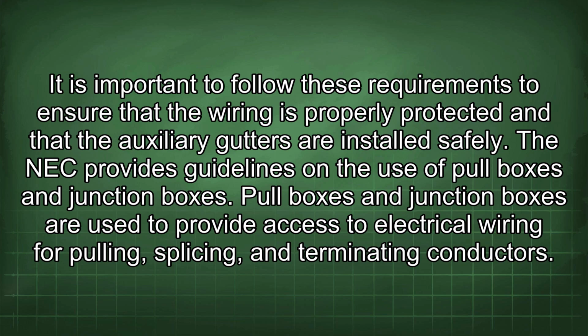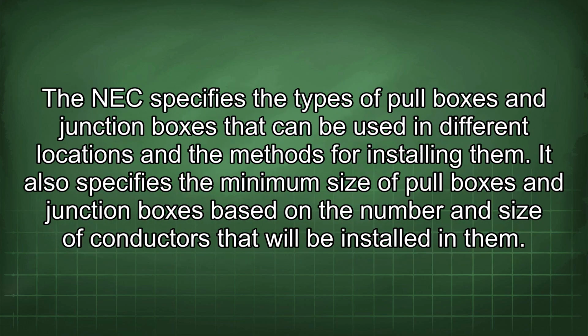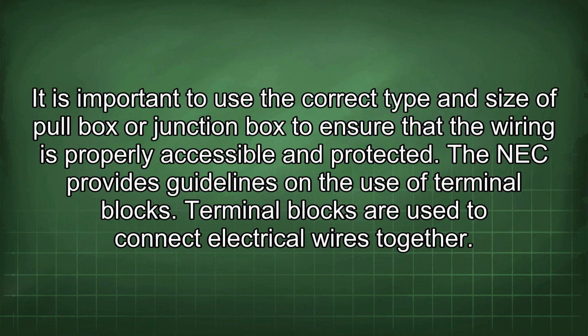Pull boxes and junction boxes are used to provide access to electrical wiring for pulling, splicing, and terminating conductors. The NEC specifies the types of pull boxes and junction boxes that can be used in different locations and the methods for installing them. It also specifies the minimum size of pull boxes and junction boxes based on the number and size of conductors that will be installed in them. It is important to use the correct type and size of pull box or junction box to ensure that the wiring is properly accessible and protected.